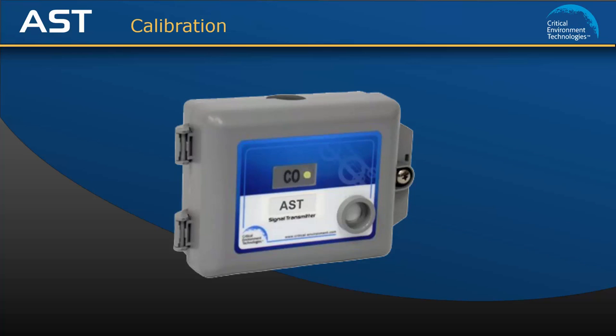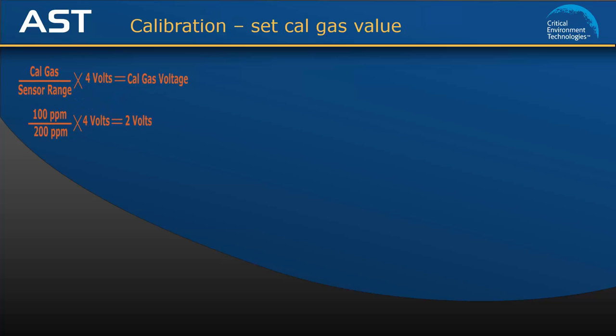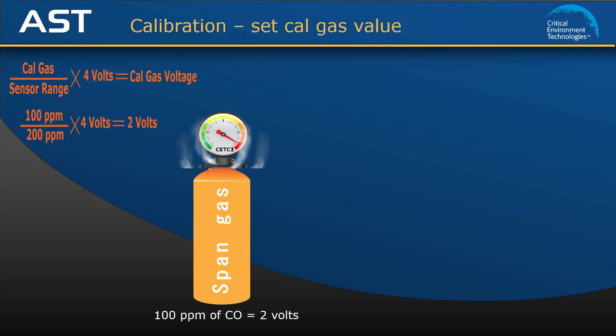The first step in calibration is to set the calgas value. To calculate the value that needs to be set, you must use the formula shown on the screen. The values we know are the factory set calgas default for CO, which is 100 ppm, and the CO sensor range, which is 0 to 200 ppm. Using the formula, we are able to calculate that the calgas value for CO is 2 volts.